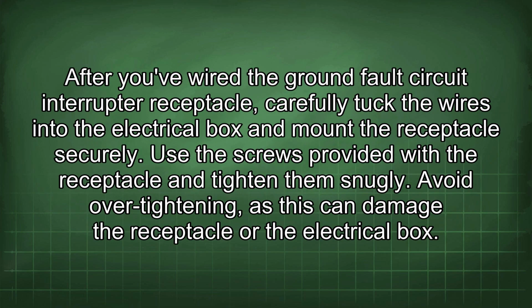After you've wired the ground fault circuit interrupter receptacle, carefully tuck the wires into the electrical box and mount the receptacle securely. Use the screws provided with the receptacle and tighten them snugly. Avoid over-tightening, as this can damage the receptacle or the electrical box.